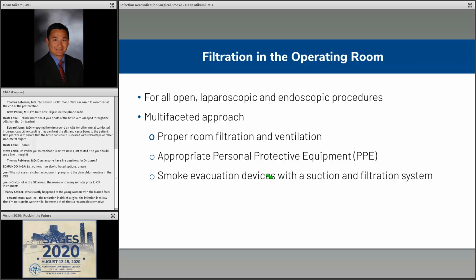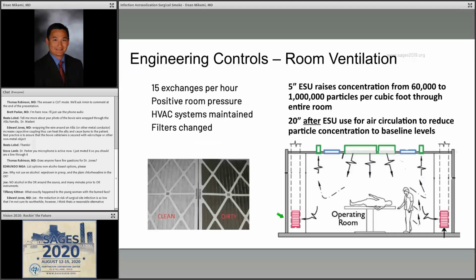It should be used for all laparoscopic, open, and endoscopic procedures. We use a multifaceted approach: proper room filtration, ventilation, appropriate PPE wear in the operating room, and smoke evacuation devices with a suction filter, most preferably an ULPA filter. So engineering controls in the OR that we use, usually every operating room has a standard 15 exchanges per hour. So every 4 minutes, the room air should be filtered through.